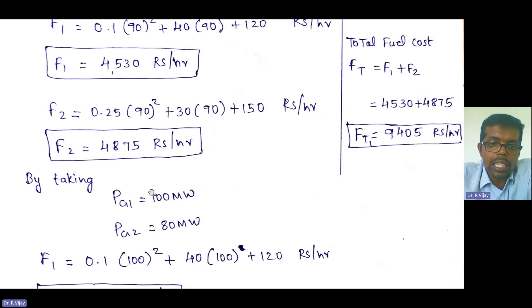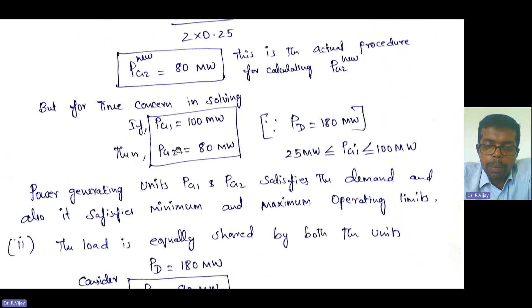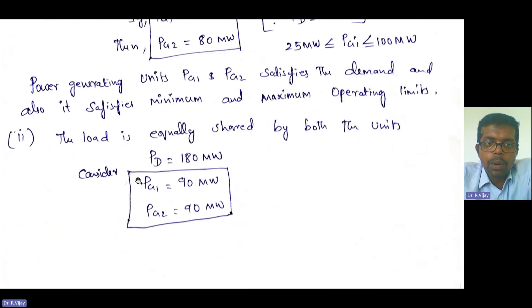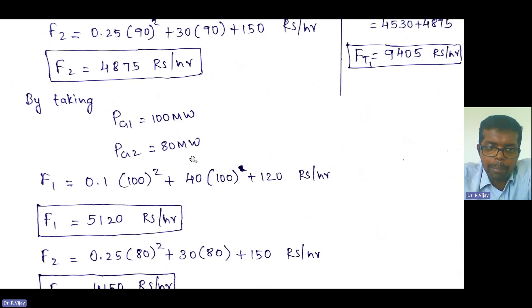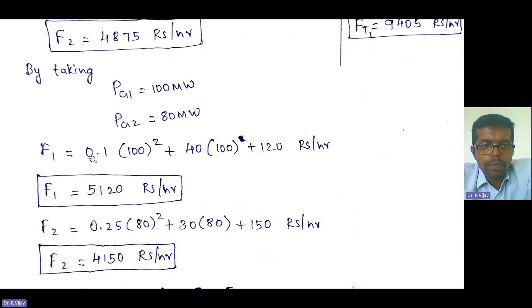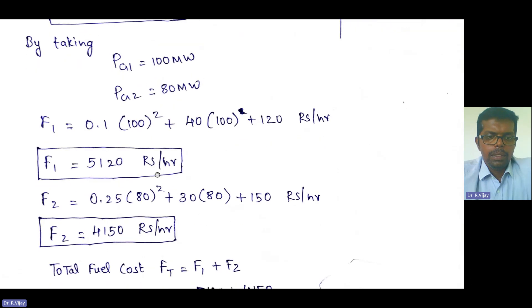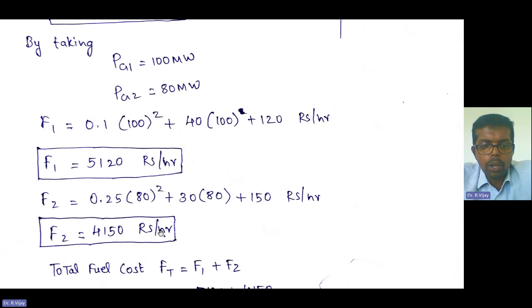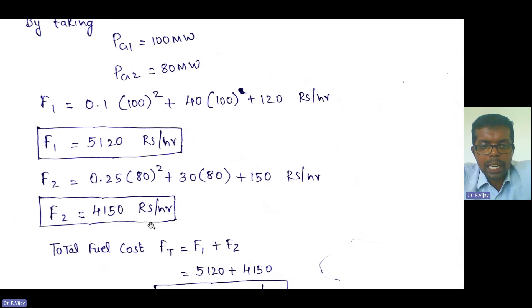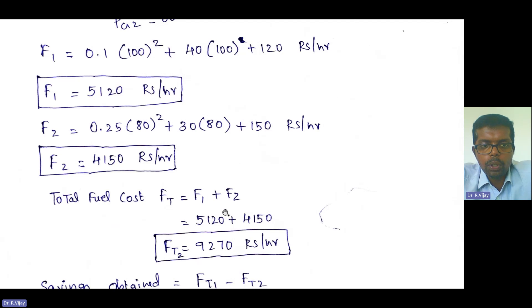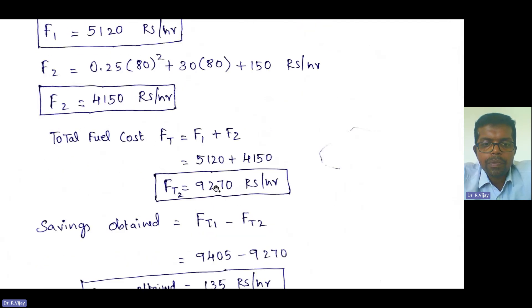Now calculate the total fuel cost using the economic load dispatch values: PG1 = 100 megawatt, PG2 = 80 megawatt. Substituting PG1 = 100 megawatt into F1 gives fuel cost F1 = 5120 rupees per hour. Substituting PG2 = 80 megawatt into F2 gives fuel cost F2 = 4150 rupees per hour. Total fuel cost from economic load dispatch = 5120 + 4150 = 9270 rupees per hour.